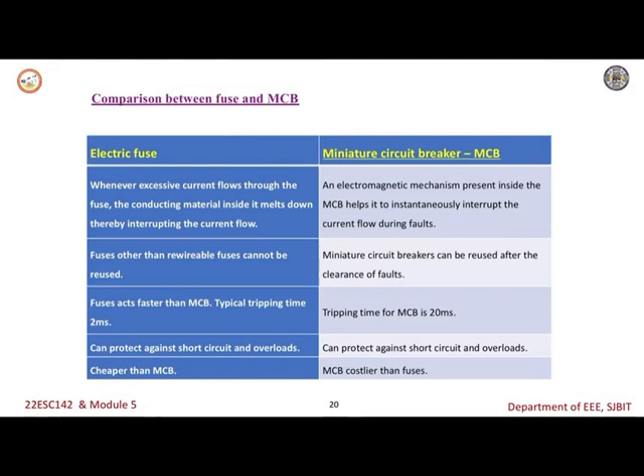Fuses other than rewirable fuses cannot be reused. But a miniature circuit breaker can be reused after the clearance of the fault. Whenever an overload happens, we can manually turn on the MCB and restore the supply. That is the advantage compared to the fuse. Next, if you compare, the fuse acts faster than the MCB. As we said earlier in the disadvantages, the disadvantage of the MCB is slow tripping.